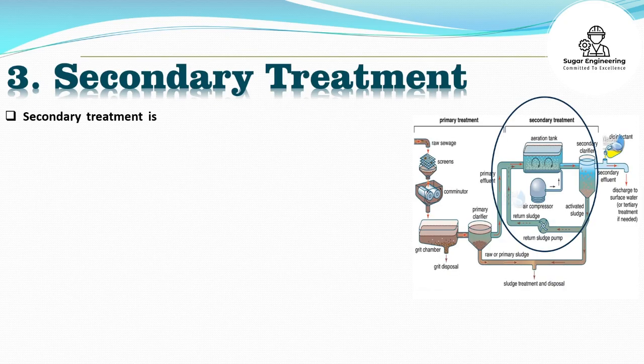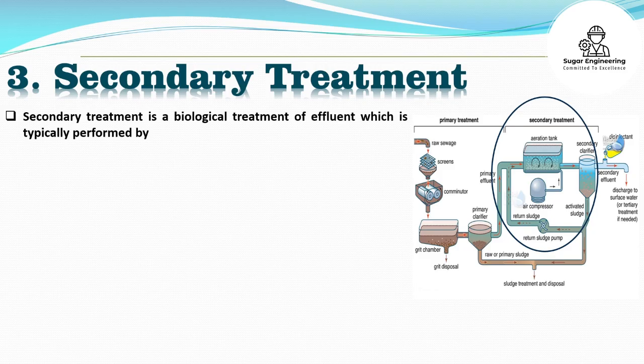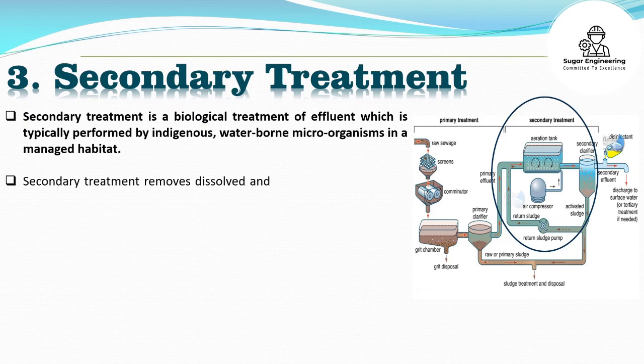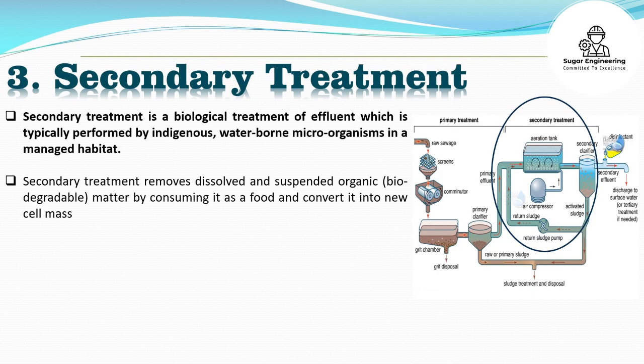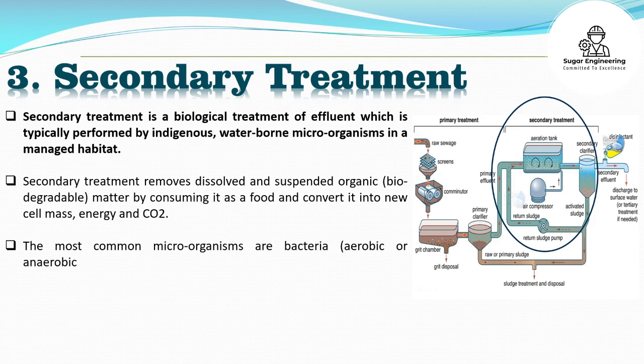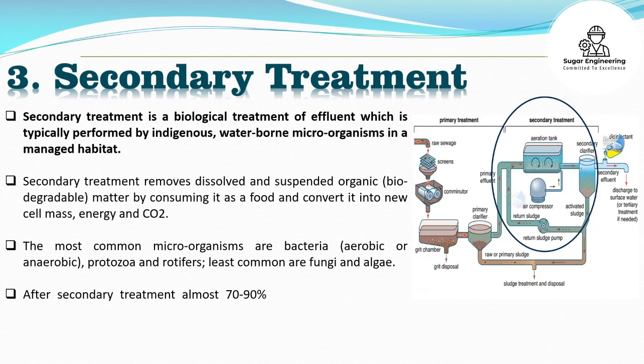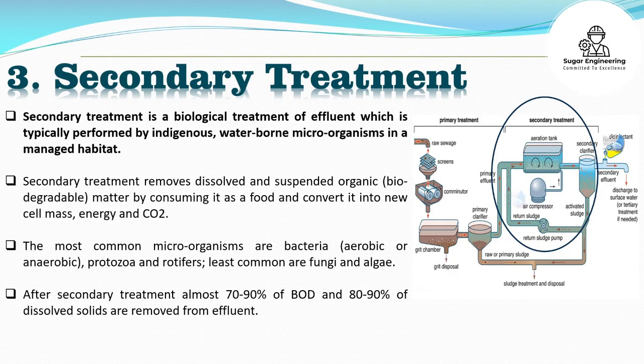Secondary treatment is a biological treatment of effluent, which is typically performed by indigenous, water-borne microorganisms in a managed habitat. Secondary treatment removes dissolved and suspended organic, biodegradable matter by consuming it as food and converting it into new cell mass, energy, and CO2. The most common microorganisms are bacteria (aerobic or anaerobic), protozoa, and rotifers. Least common are fungi and algae. After secondary treatment, almost 70 to 90% of BOD and 80 to 90% of dissolved solids are removed from effluent.